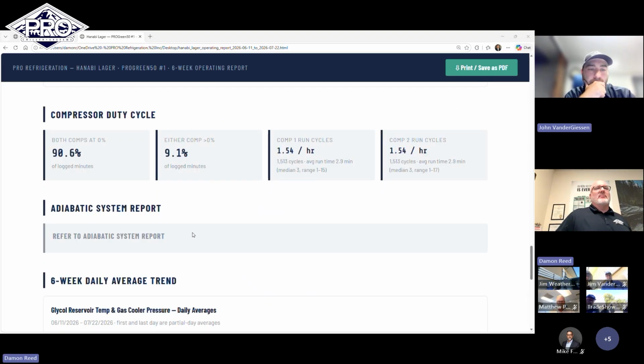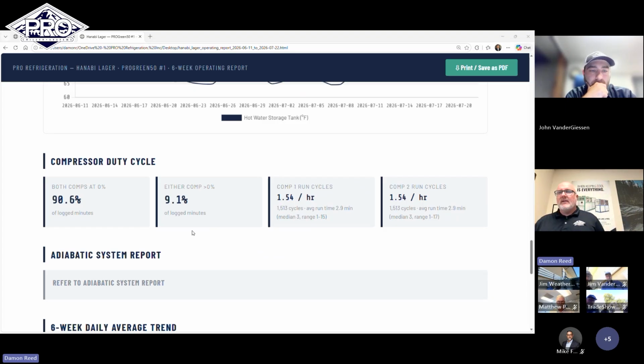So duty cycles on the compressors. This is a really solid one. I think that says a lot about the last 6 weeks. Both compressors at 0%, 90% of the time. We haven't even operated compressors. We've run 9% of the time. Our run cycles have averaged 1.5 per hour with an average runtime of 2.9 minutes. Even runtime on both compressors, that's great to see. What that tells me is there just hasn't been a lot of load on the system over the past 6 weeks.